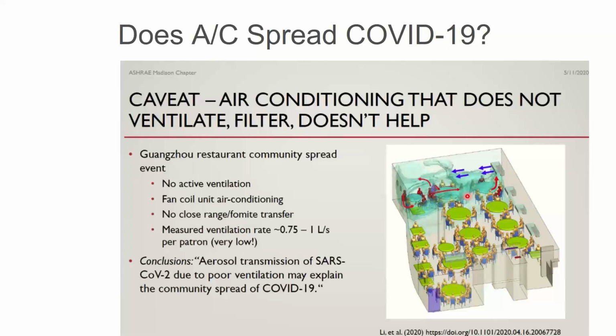Well, technically, if you look at the slide, it says they had 0.75 liters per second. I don't know what the heck that is because I don't deal with liters. So when I converted that, that's 2.1 CFM, cubic feet per minute. That is basically zero. As you're going to see in a little bit, most of the codes are going to be looking for 15, 20 plus CFM per person of outside air at a legal minimum. This is like 1/10 of the legal minimum of fresh air.